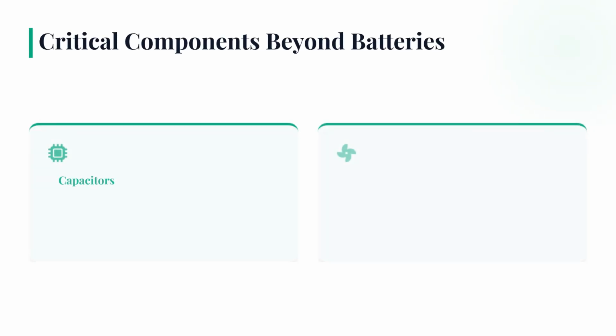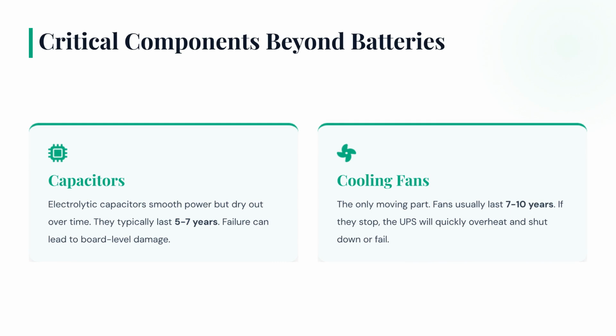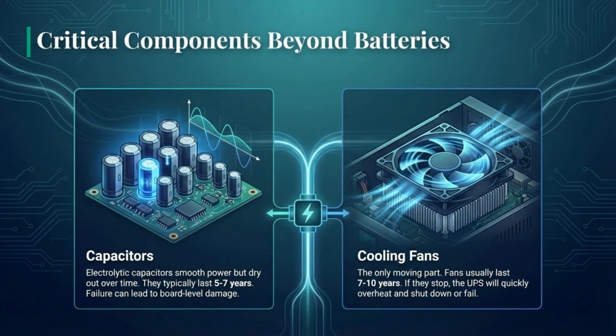Beyond batteries, critical components include capacitors, which typically last 5 to 7 years. Failure can cause board damage. Cooling fans are the only moving parts and usually last 7 to 10 years. Failure leads to overheating. Maintaining these non-battery components is crucial to maximizing the service life of the entire UPS system.